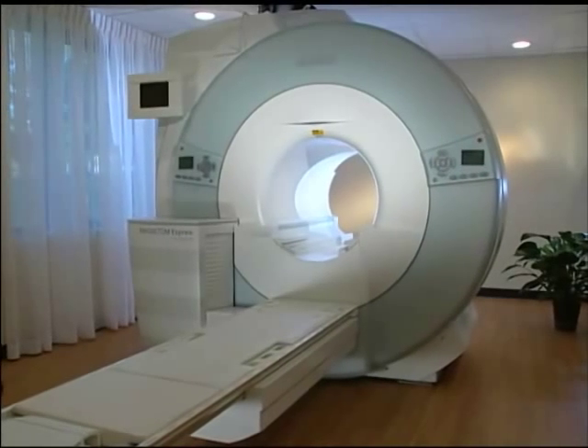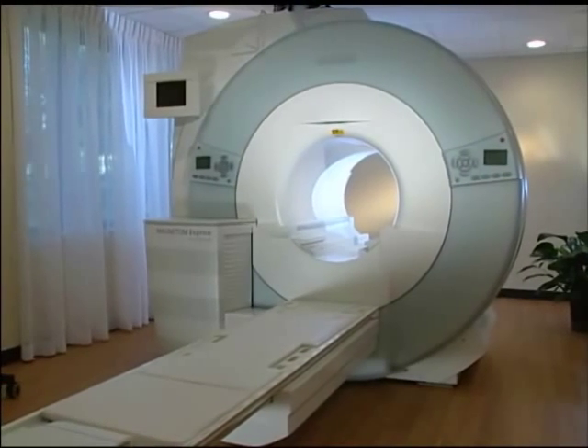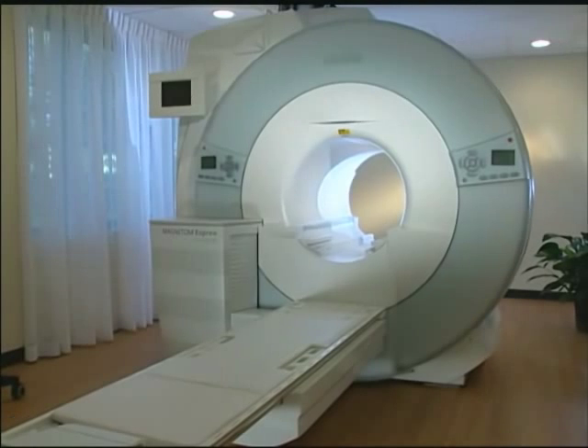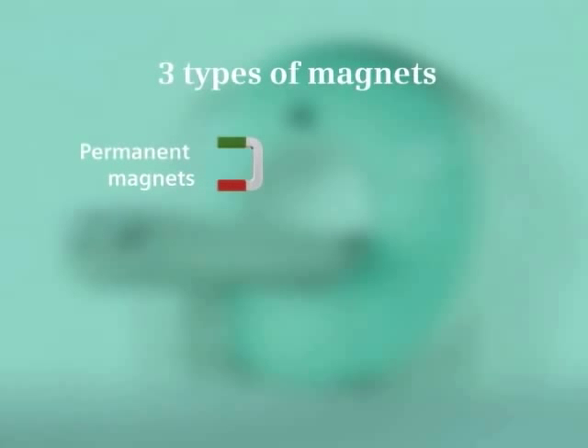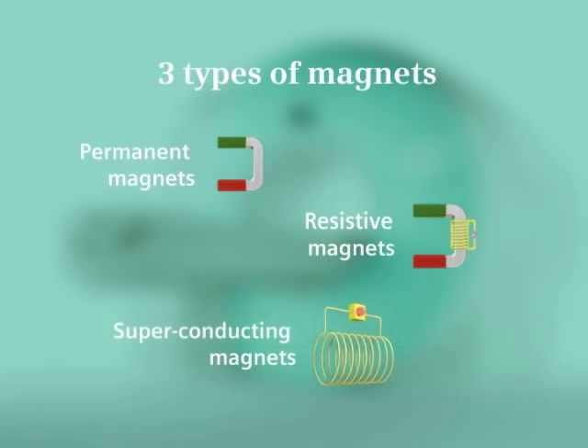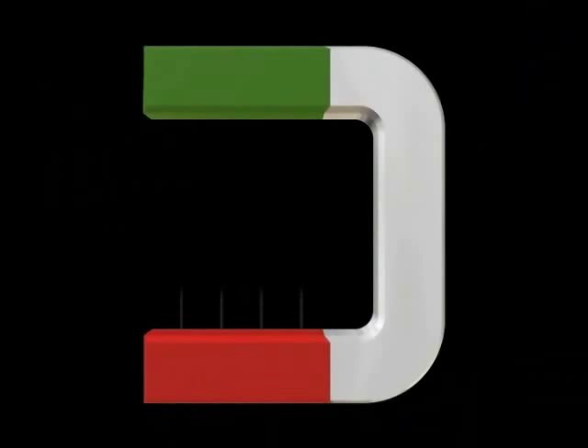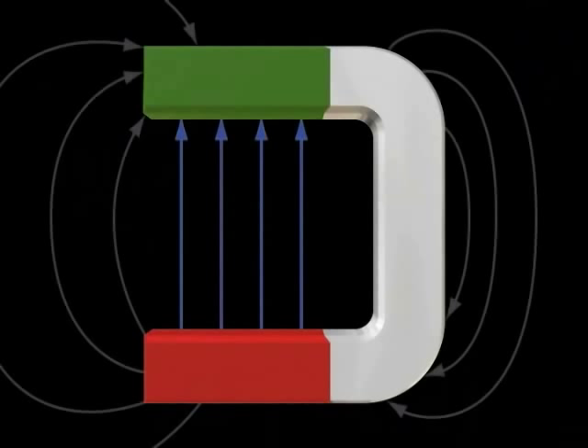Now let's take a look at the core of the MR system — the magnet. There are three types of magnets used in clinical imaging: permanent magnets, resistive magnets, and superconducting magnets. Permanent magnets always have a magnetic field. In case of an emergency, a permanent magnet cannot be switched off. They do not require an external energy supply and can only reach limited field strengths.